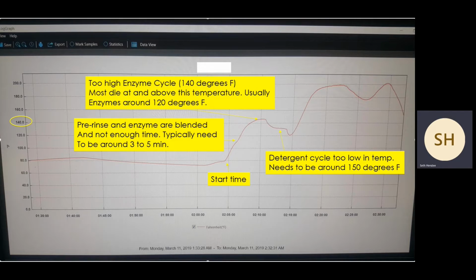Pre-rinse and enzyme are blended, but there's not enough time. It typically needs around 3 to 5 minutes, and this one is short. It's less than 3 minutes. The next phase that happens is we go into the enzyme cycle, and that cycle was too hot, right? 140 degrees. Most enzymes die at or above this temperature, right? Usually enzymes should be at 120. So this is 20 degrees warmer than most manufacturers would recommend their enzymes being used. So instead of those enzymes giving us the cleaning action that we want, that they're supposed to help with, we've killed them off because it's too hot, and now they're inactive, and now we wonder why our washer doesn't perform as well as it should.